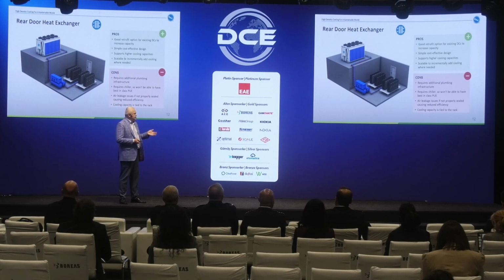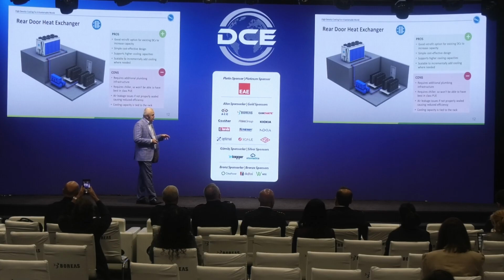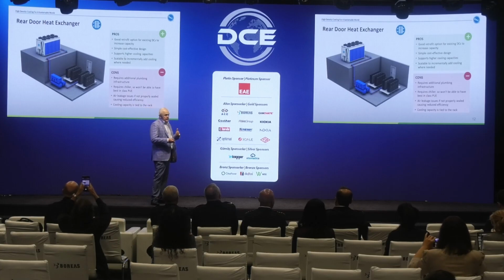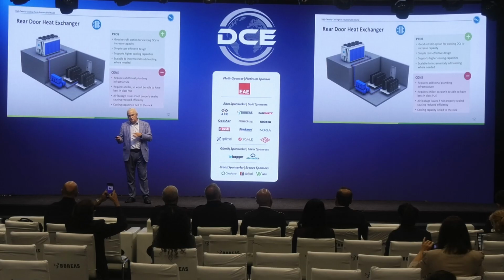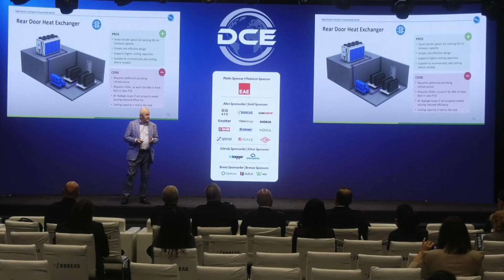Rear door heat exchanger is a very simple technology, but the problem is still the chiller. It's a very good method if you already have a data center to retrofit, switching from air cooling to increase density per rack. It's easy to retrofit.